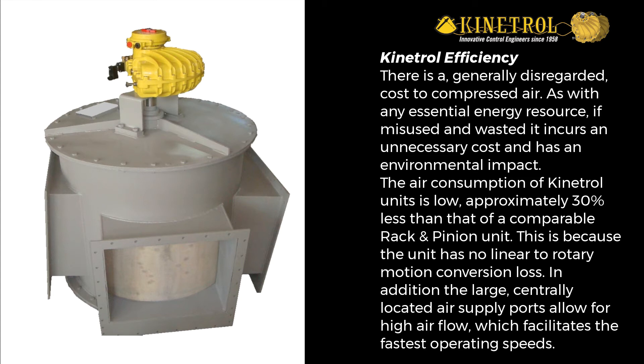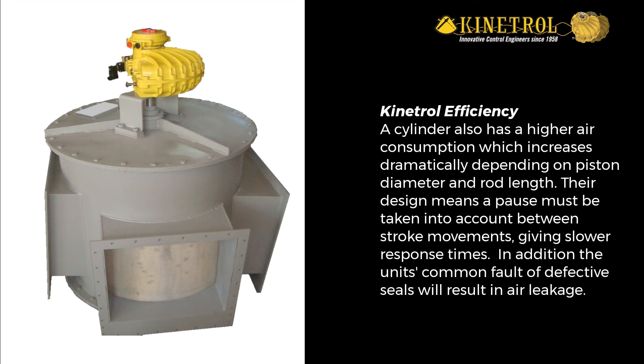This is because the unit has no linear-to-rotary motion conversion loss. In addition, the large centrally located air supply ports allow for high air flow, which facilitates the fastest operating speeds. A cylinder has a higher air consumption which increases dramatically depending on piston diameter and rod length. Their design means a pause must be taken into account between stroke movements, giving slower response times, and the unit's common fault of defective seals will result in air leakage.